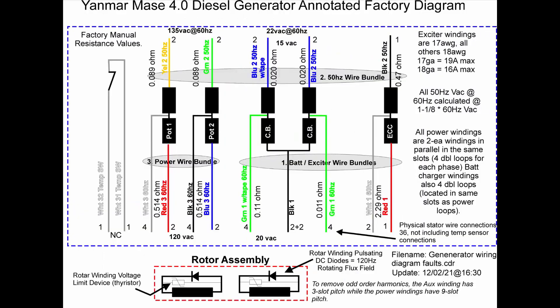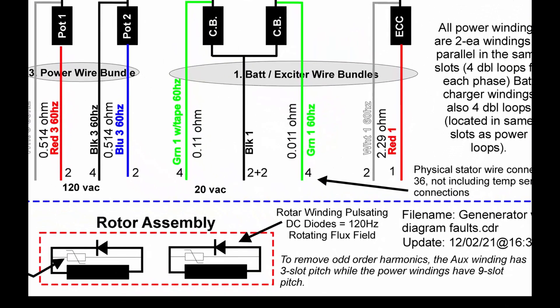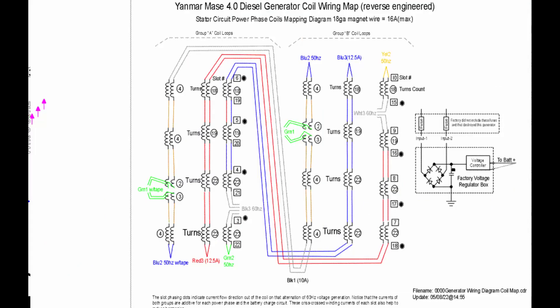After reading through several patents, I discovered that as stated here, to remove odd-order harmonics, auxiliary winding has three-slot pitch, while the power windings have nine-slot pitch. Also the rotor winding pulsating DC diodes equals 120 Hz rotating flux field. So this 120 Hz rotating flux field is what allows the mixing to cause the harmonics. And the third-order harmonic is the worst one. So the slot arrangement of the windings compensates for that.